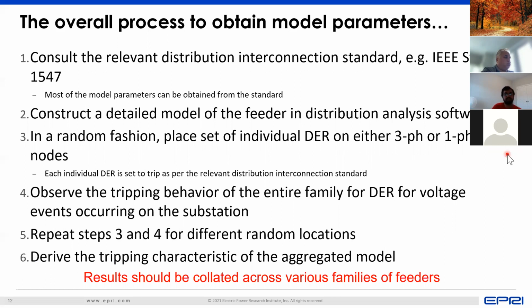And from the EPRI side, we provide the thought process and the technology transfer and the learnings to the distribution utilities, to the transmission utilities, so that they can make use of these results in improving their efficiency in their study process. So the approach that we take is, once we have this detailed model constructed, we construct this detailed feeder. We do a lot of random studies on this feeder in terms of the location of the DER, in terms of the tripping characteristics that we have. And we really look at different kinds of feeders, different families of feeders, and then we collate them together to derive the tripping characteristic of the aggregated model. And once we have this tripping characteristic, we then derive a set of generic parameters, and we can say that if you use these generic parameters, you are going to get a representation of the behavior of DER in the system, which you can then use for your planning studies.